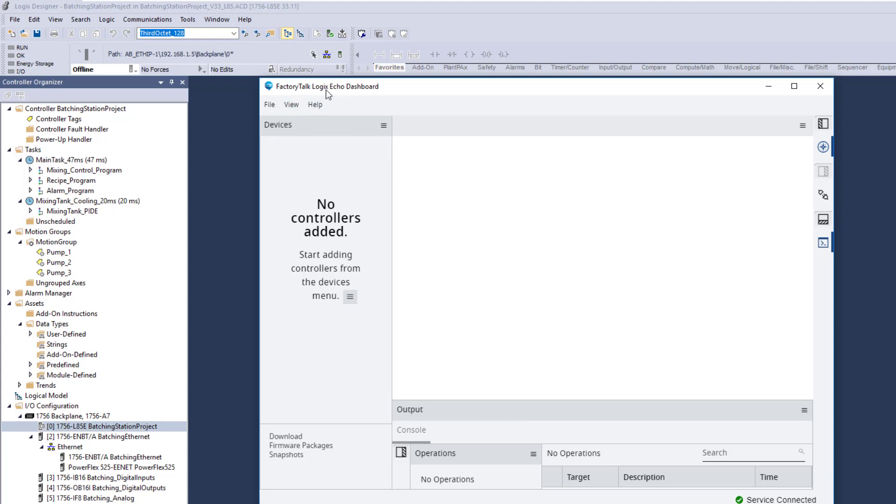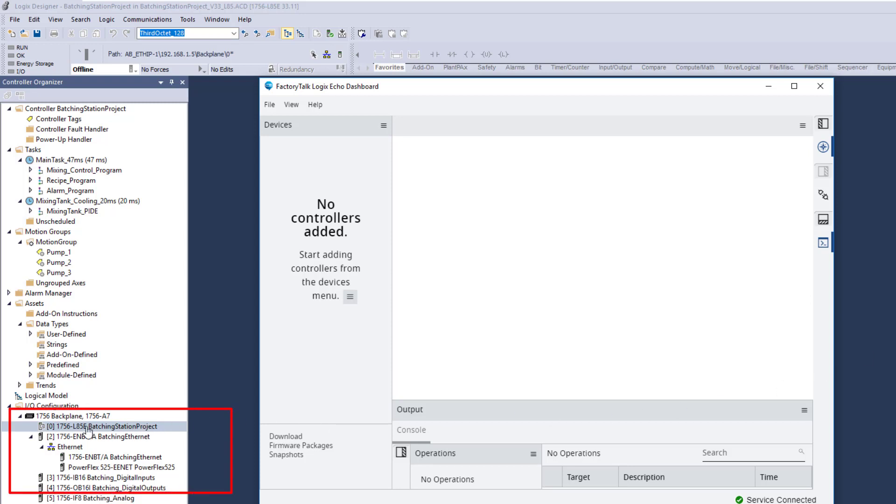So the cool thing about FactoryTalk Logix Echo is you can take your project in whole the way it is, meaning the way it's going to run in the field, the way you designed it to run in the field permanently, and you can echo that all in an emulated environment without using an emulated processor. So what does that mean for us? That means we don't have to actually change our processor. You don't have to change our processors to an emulated processor like we have done in the past. The drawback to this is it's only going to be an L8 processor or above.